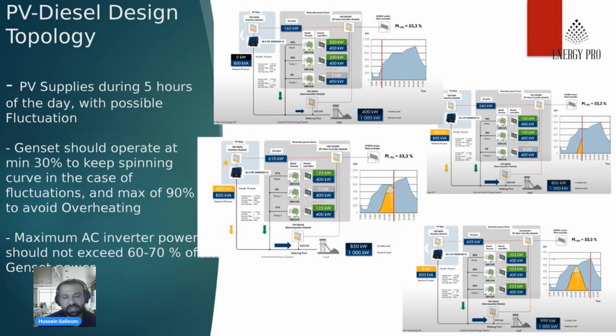And this 30% is very important for the spinning curve, because in the case of fluctuations, the generator should be there ready to take the load from the solar. So that's why we have to keep it running at minimum 30%. Some generators could be 25%, but for the calculation now, we'll consider it as 30%, and it should not run more than 90% to avoid any kind of overheating. That's why we recommend to put as many generators as possible, either with smaller sizes, to keep that flexibility available.